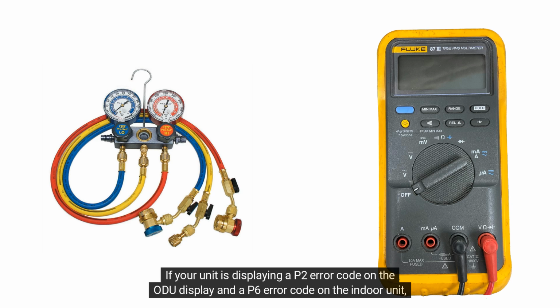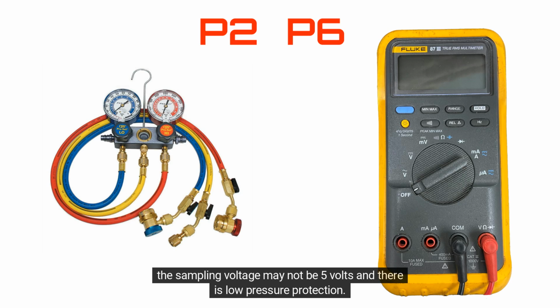If your unit is displaying a P2 error code on the ODU display and a P6 error code on the indoor unit, the sampling voltage may not be 5 volts, and there is low pressure protection. To troubleshoot, you will need your refrigeration gauges and a multimeter.